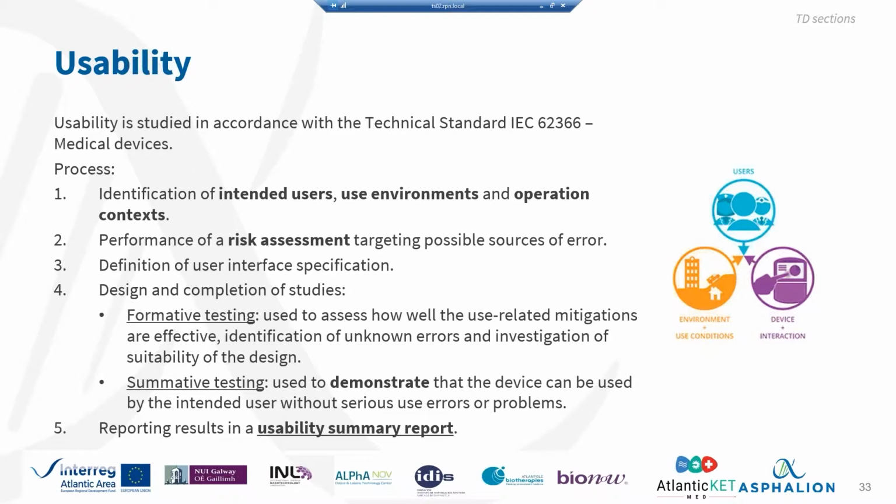Why? Because it's important to take into account this usability feedback before you have closed all the aspects of your device. Maybe your device has excellent performance and is very safe, but when the doctor has to use it, he doesn't know how, and then he uses it incorrectly, which leads to bad consequences. So it's important to have this input, this formative testing, early in the development, so as to be able to implement these ideas in the design.